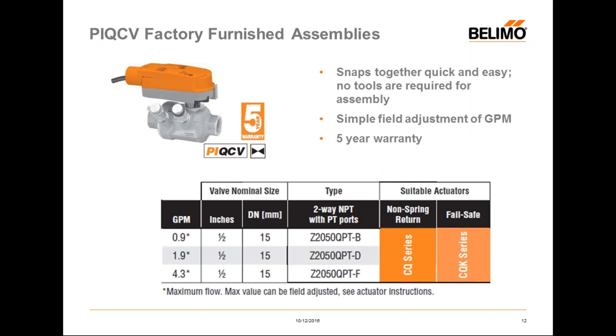The PI-QCV product range consists of three valves today: a max GPM value of 0.9, 1.9, and 4.3. At this point they're all half-inch valves, available with the CQ actuator in failsafe and non-failsafe options. The QCV product range also includes failsafe and non-failsafe actuators. On the PI-QCV, they snap together quickly and easily without tools, GPMs can be field-set, and they're covered by a five-year warranty.